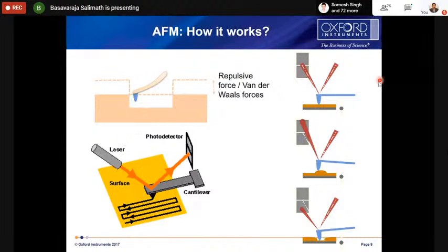To know that, what we are doing is taking a laser and aligning it at the end of the cantilever, and the reflected laser goes to the photodetector. This is a position sensitive photodetector, meaning the position of the reflected laser will be noted down at each pixel while it's scanning. Now you can see here it's almost flat, so the reflected laser is at the center. But when the tip comes onto some kind of particle, the tip goes up, and the reflected laser also goes up. The same way, if some pit comes in the surface, the tip goes down, and here also the laser spot will go down on the photodetector.